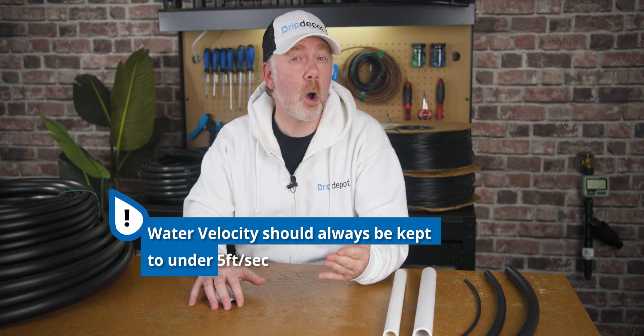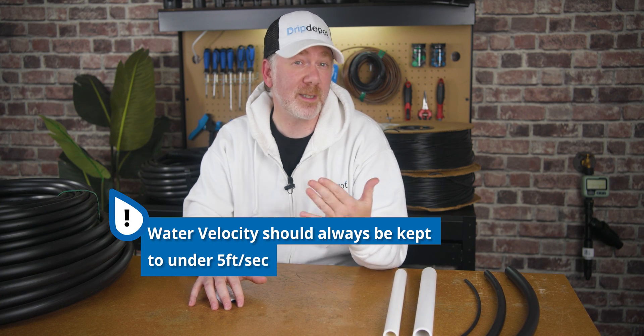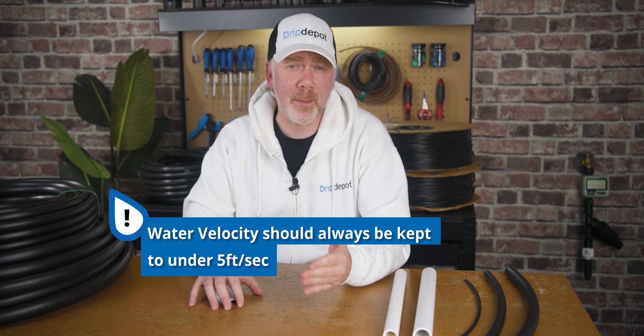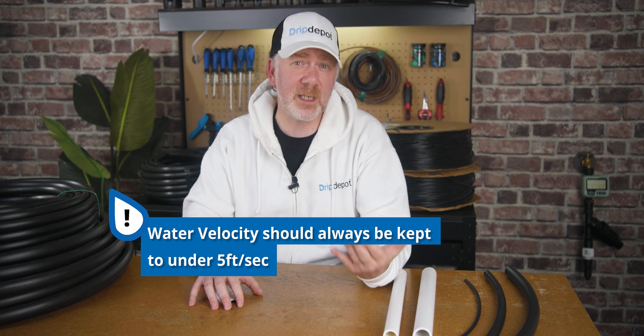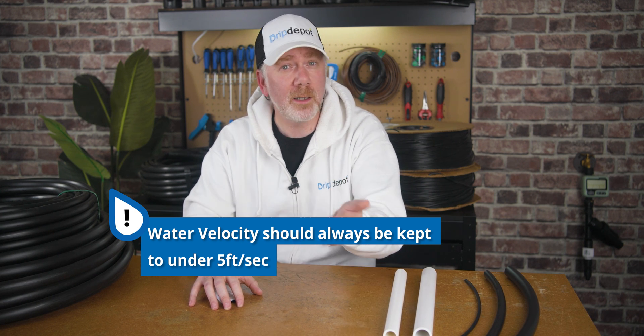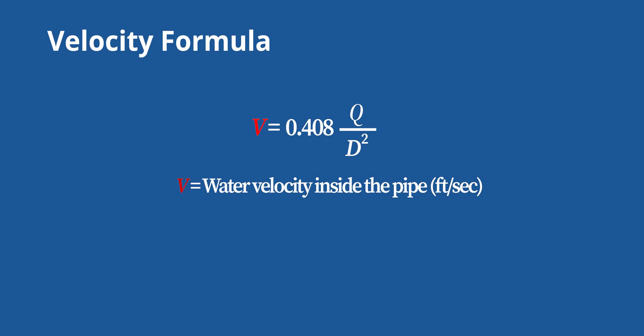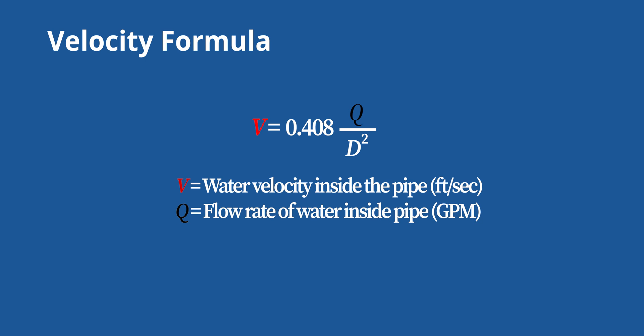Let's touch a bit on velocity. The general rule in the irrigation industry is that water velocity should always be kept under five feet per second. Higher than that and components can become damaged, particularly fittings like elbows and tees, and important components like valves. Unlike friction loss, we don't need to know the linear length of our line to determine velocity. On the screen now, and linked in the description, is the formula you can use to determine velocity. All you need to know is the flow rate in gallons per minute and the inside diameter of your tubing or pipe.